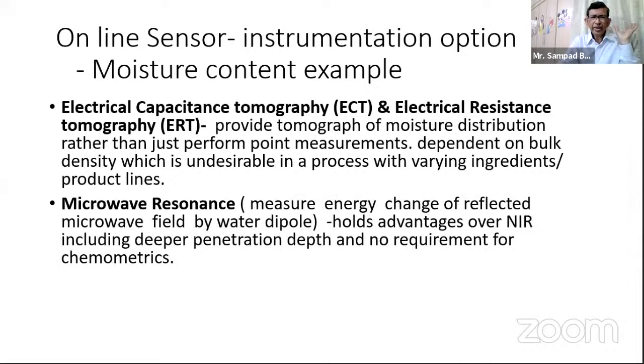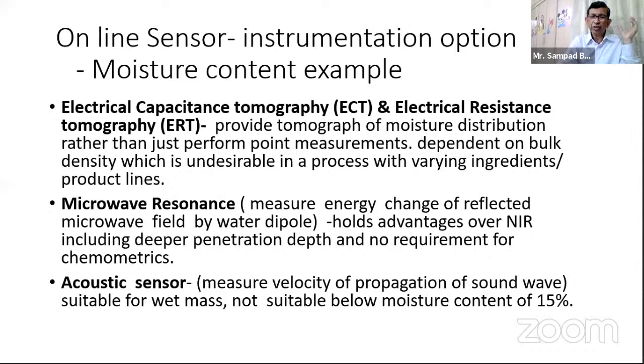Microwave resonance works on the energy change of the reflected microwave field by the water dipole. It holds advantages over NIR, including deep penetration depth and no requirement for a chemometric model for interpretation. NIR and similar methods are a little sophisticated and need a chemometric tool to really interpret. The acoustic sensor measures the velocity of propagation, sometimes reflection, of a suitable wet mass. It is suitable for wet mass, not for moisture content below 15%. Maybe a very wet cake when you take it out of a crystallizer or before filtration, where moisture content may be around 15%. Sometimes it may be very wet granules. In wet granules, the water content is between 20 and 28 to 30%, where an acoustic sensor may be suitable.